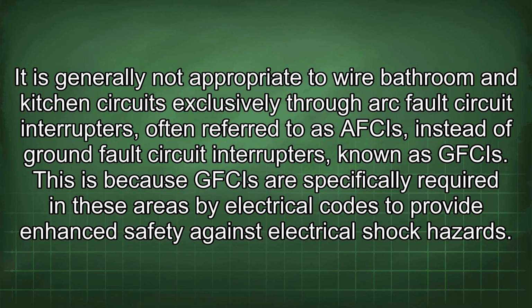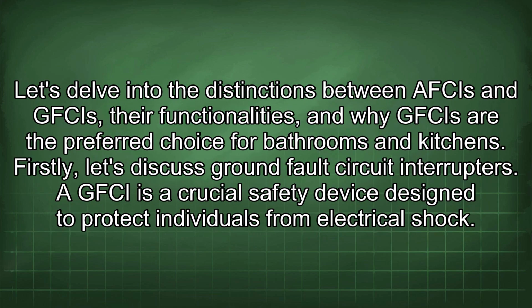It is generally not appropriate to wire bathroom and kitchen circuits exclusively through arc fault circuit interrupters, often referred to as AFCIs, instead of ground fault circuit interrupters, known as GFCIs. This is because GFCIs are specifically required in these areas by electrical codes to provide enhanced safety against electrical shock hazards. Let's delve into the distinctions between AFCIs and GFCIs, their functionalities, and why GFCIs are the preferred choice for bathrooms and kitchens. Firstly, let's discuss ground fault circuit interrupters.